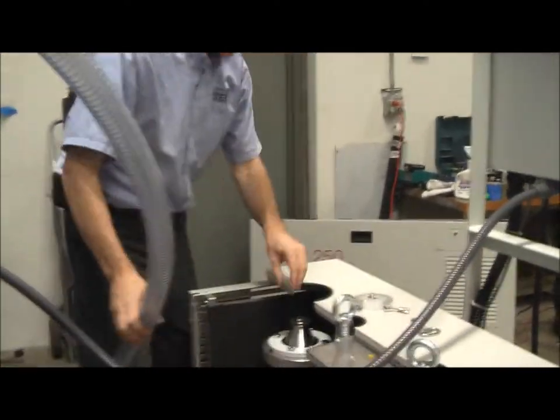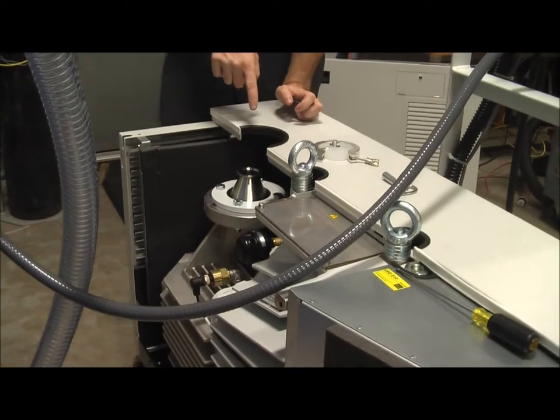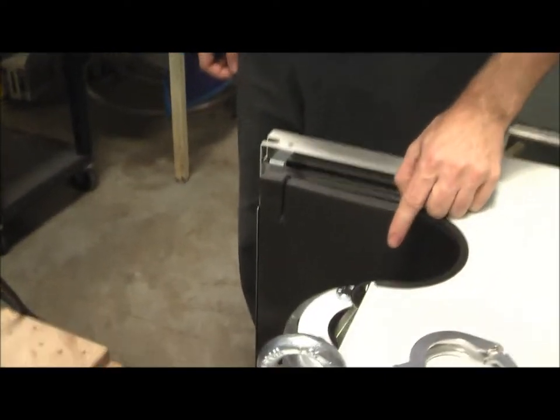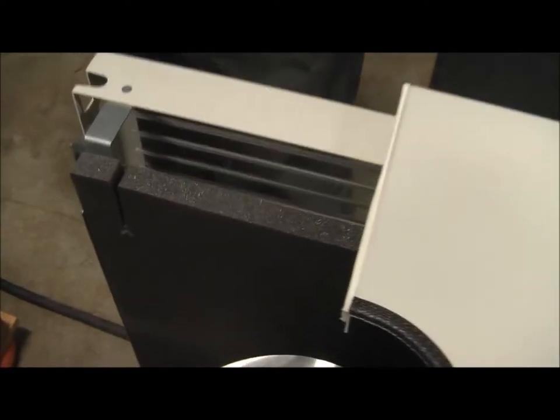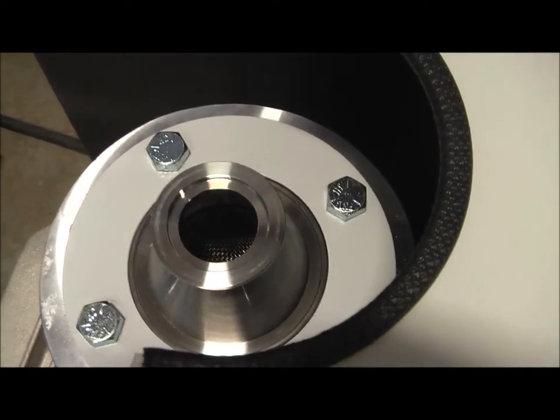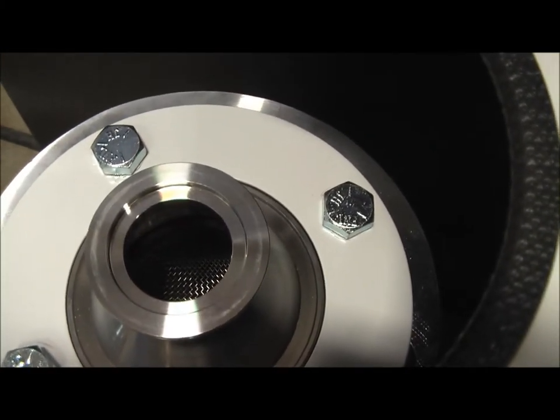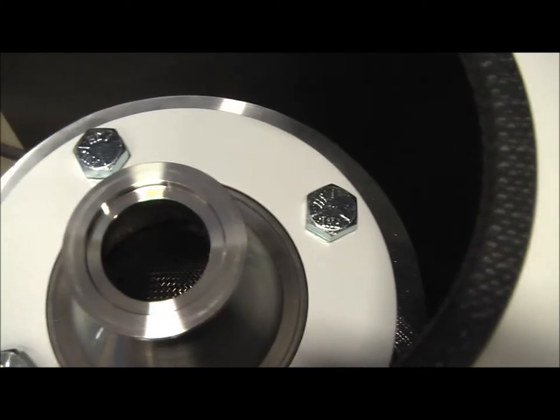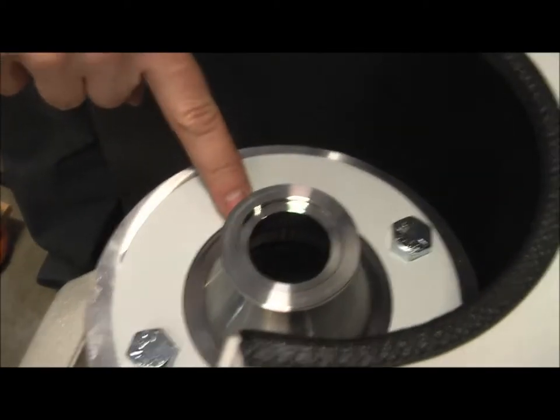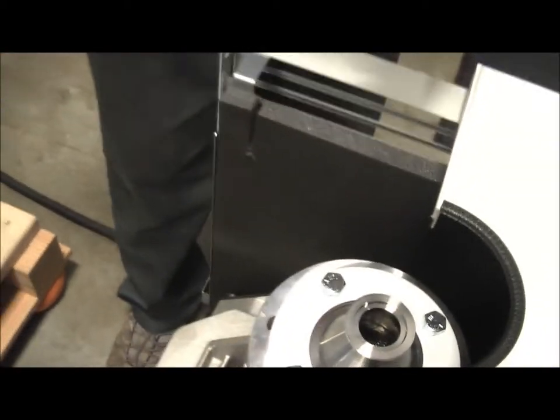Now down inside this reducer is where our screen is. This is someplace that probably on periodic maintenance we should take a look at that screen. You can see it there. Just inspect that, make sure it's not clogged, make sure there's no debris in there. If it needs to be cleaned, you'll have to take out these four big bolts and take the adapter off and remove the screen and clean it.